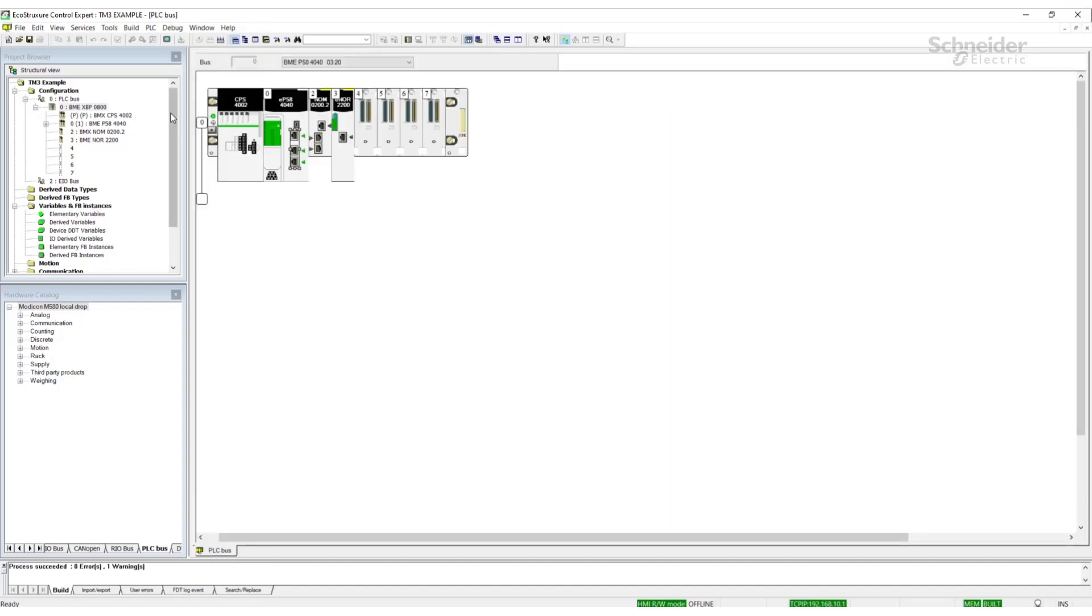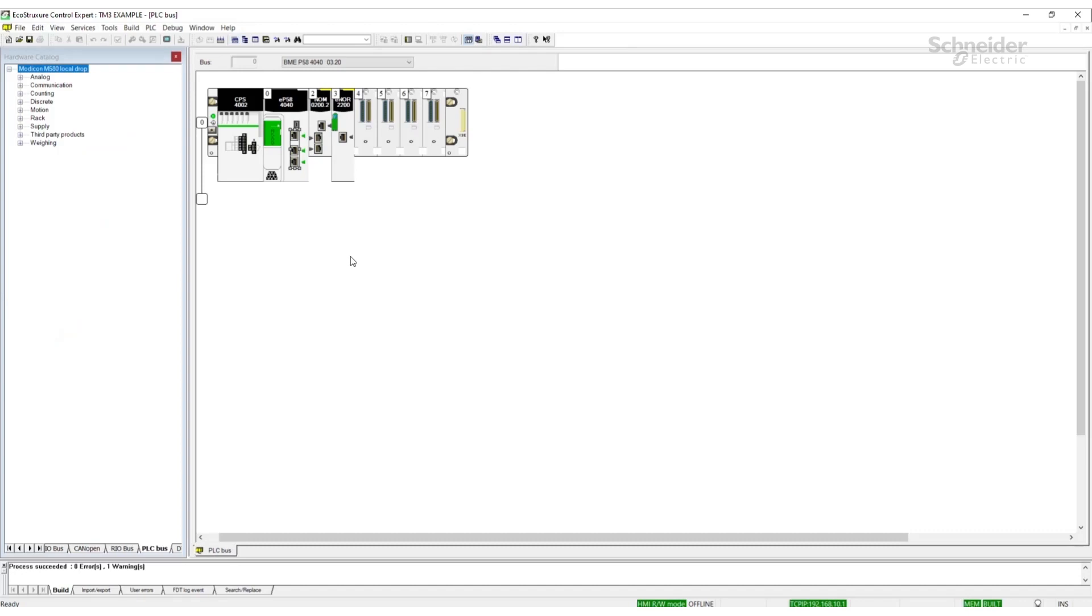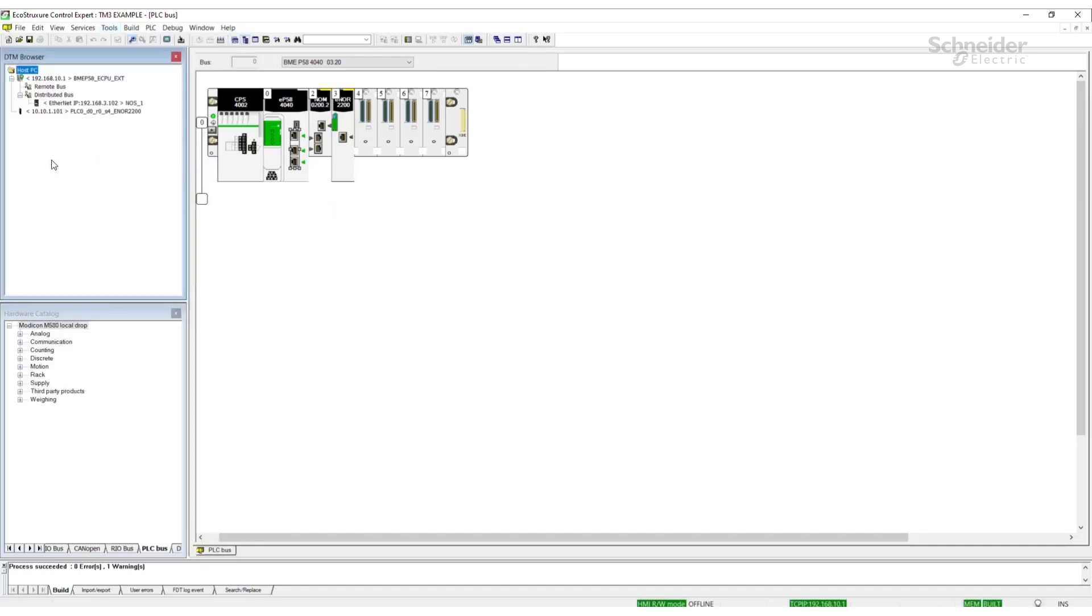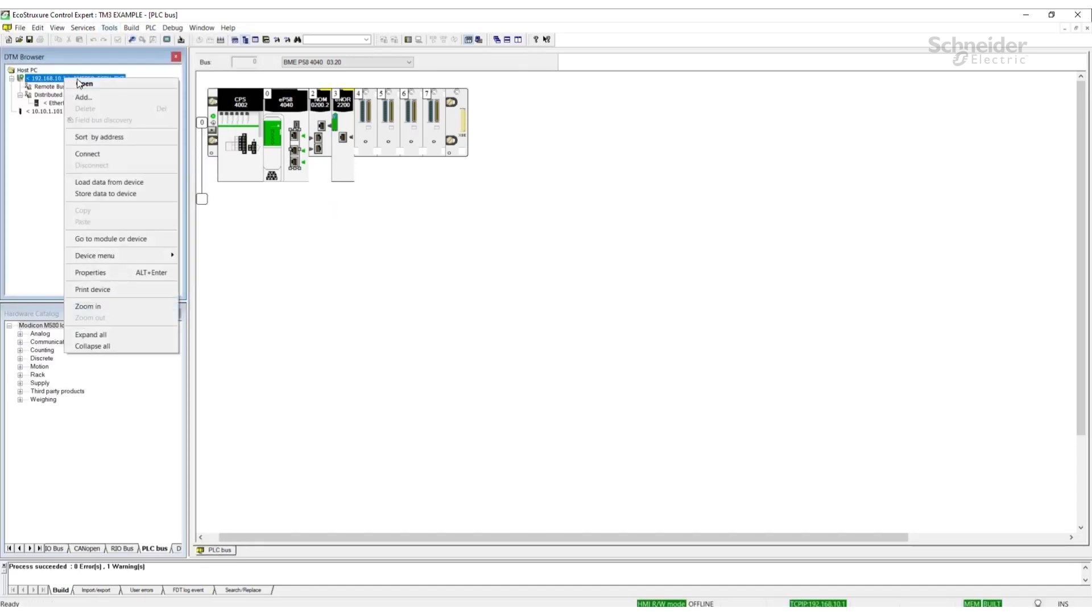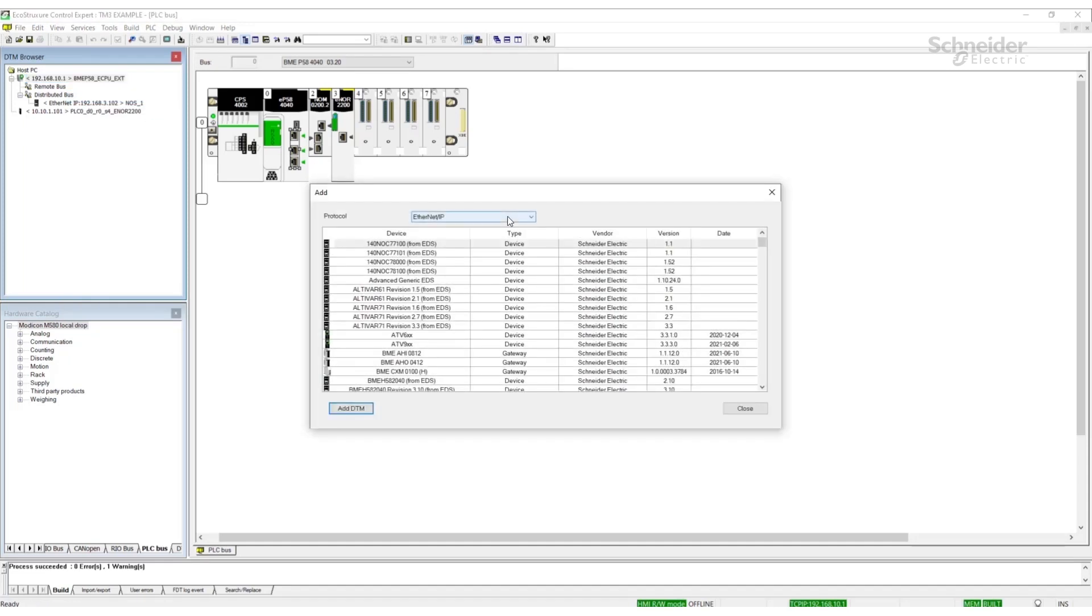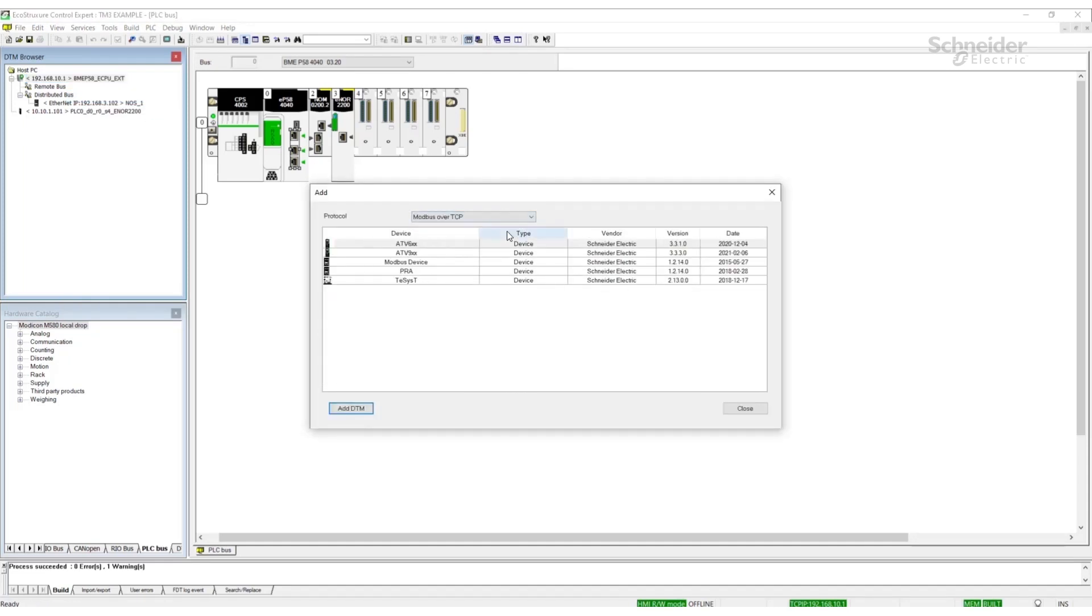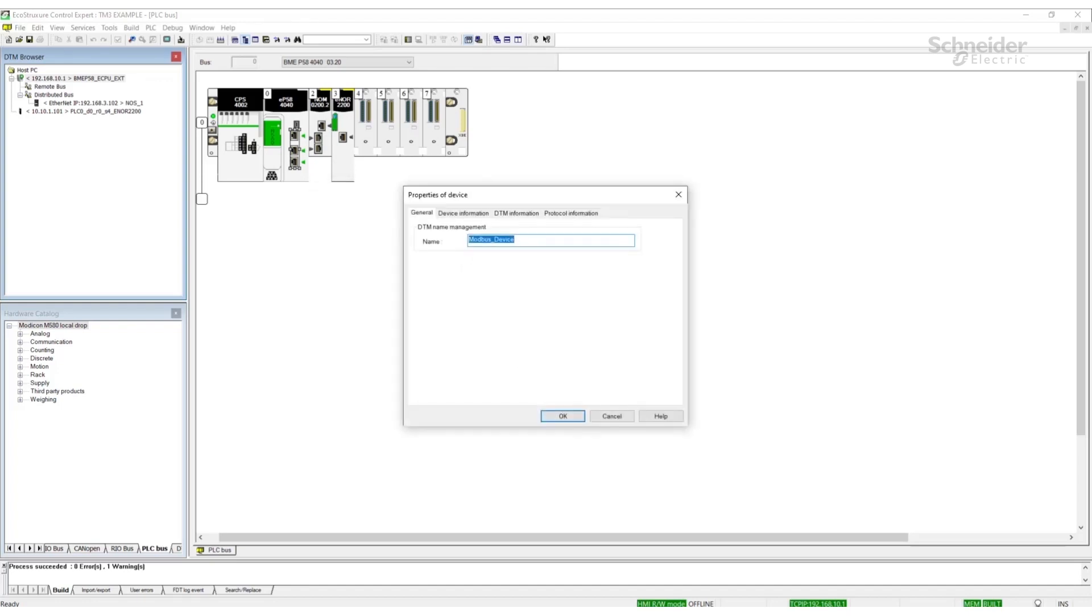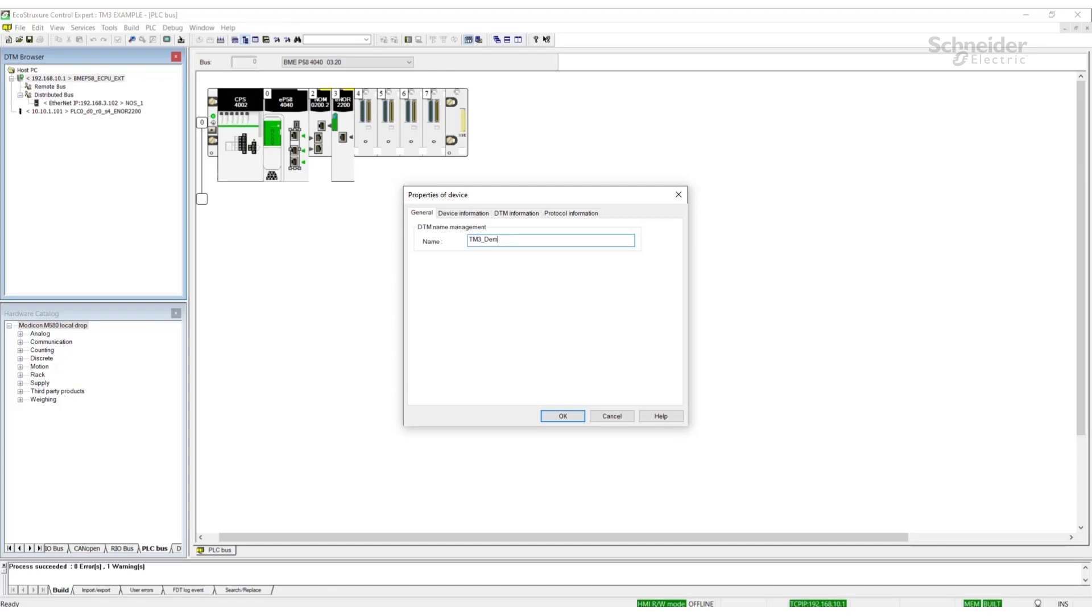To set up the communications to the bus coupler, we're going to open the DTM browser by going to Tools, DTM browser. We're going to add a Modbus device. We're going to name the DTM whatever name makes sense in the application.